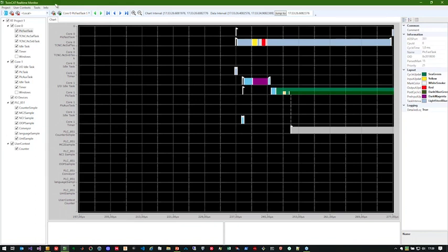But maybe you would like to have some information in case of a specific event. Then you can use this live data trigger and define a trigger prelude, where you define how much history before a specific event you need, in maximum 1 minute. And then you can do your analysis. If a specific event occurs, then all the information will be stored and you can do an offline analysis later on.